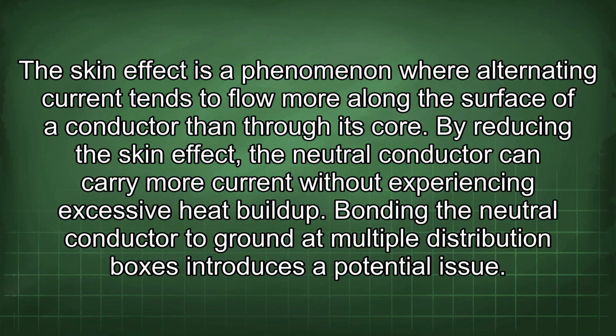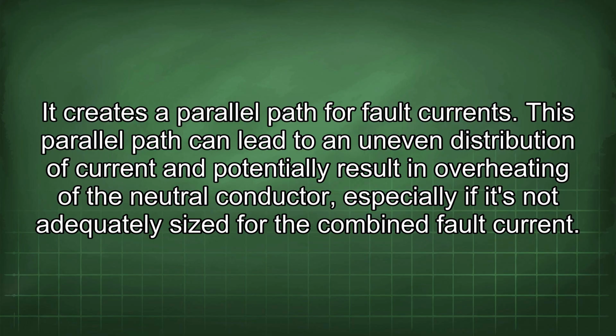Bonding the neutral conductor to ground at multiple distribution boxes introduces a potential issue. It creates a parallel path for fault currents. This parallel path can lead to an uneven distribution of current and potentially result in overheating of the neutral conductor, especially if it's not adequately sized for the combined fault current.